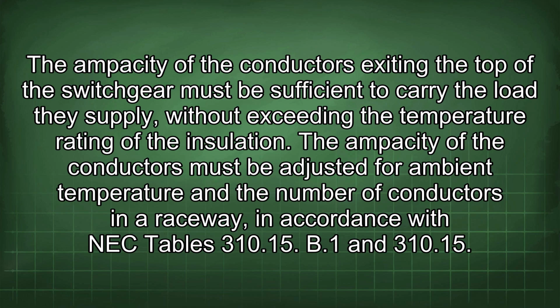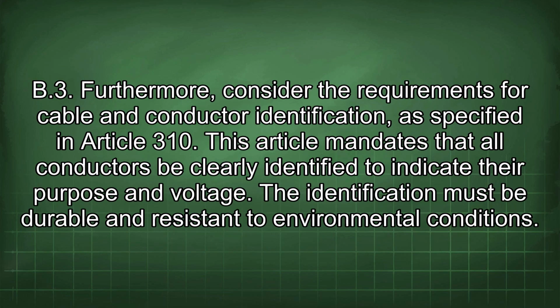The ampacity of the conductors exiting the top of the switchgear must be sufficient to carry the load they supply without exceeding the temperature rating of the insulation. The ampacity of the conductors must be adjusted for ambient temperature and the number of conductors in a raceway in accordance with NEC Tables 310.15(B)(1) and 310.15(B)(3).